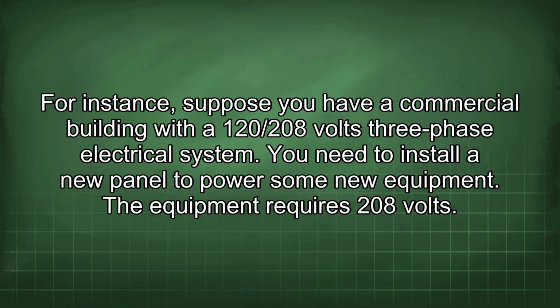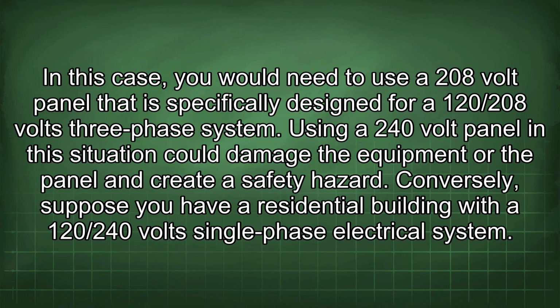For instance, suppose you have a commercial building with a 120/208 volts three-phase electrical system. You need to install a new panel to power some new equipment. The equipment requires 208 volts. In this case, you would need to use a 208-volt panel that is specifically designed for a 120/208 volts three-phase system. Using a 240-volt panel in this situation could damage the equipment or the panel and create a safety hazard.